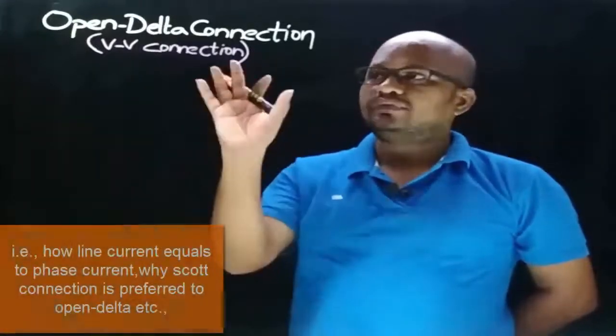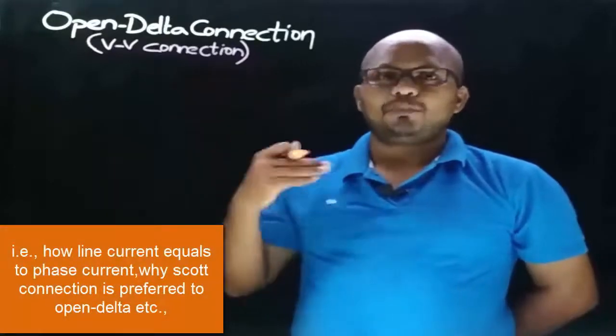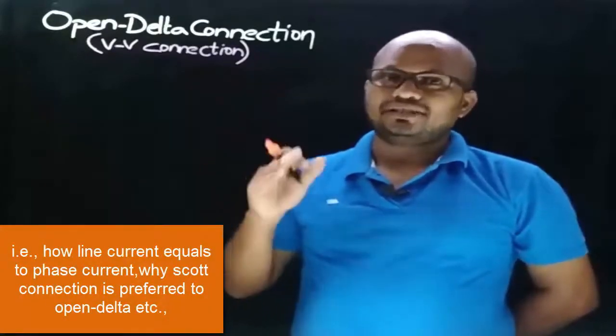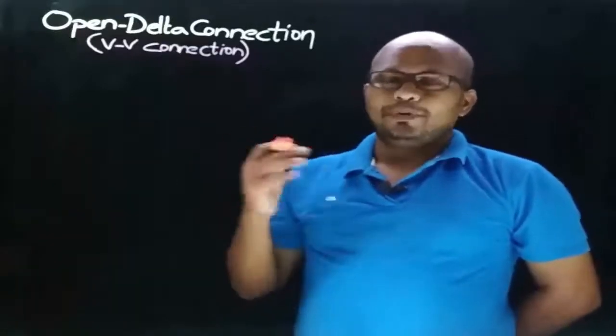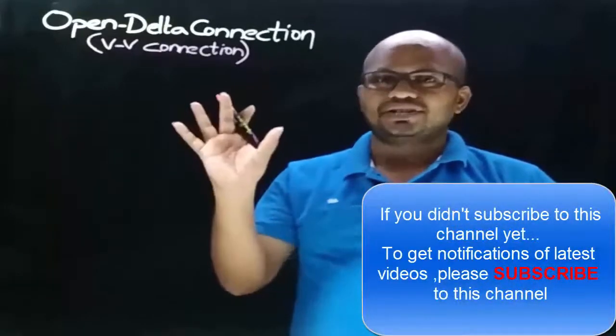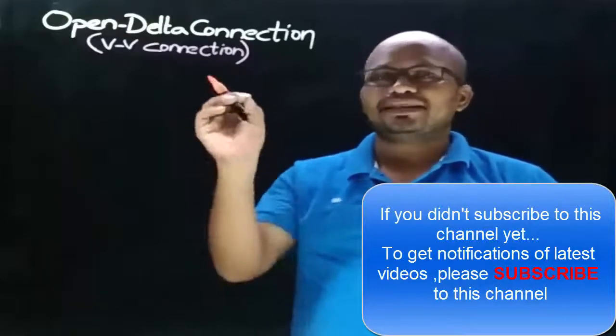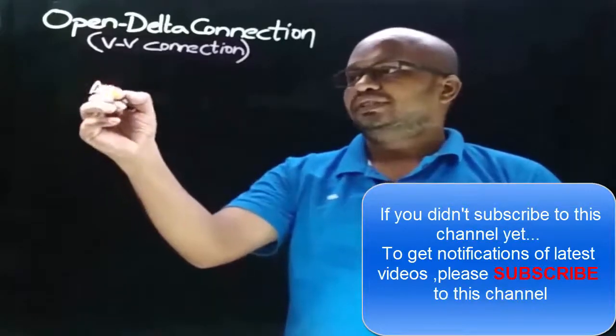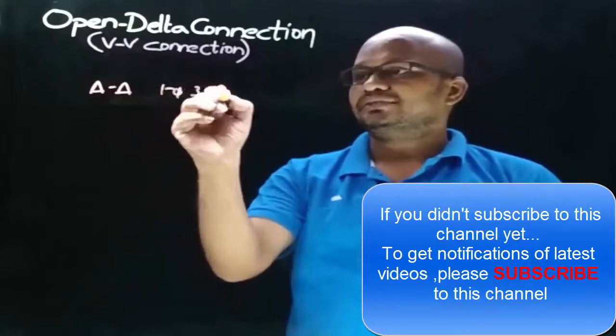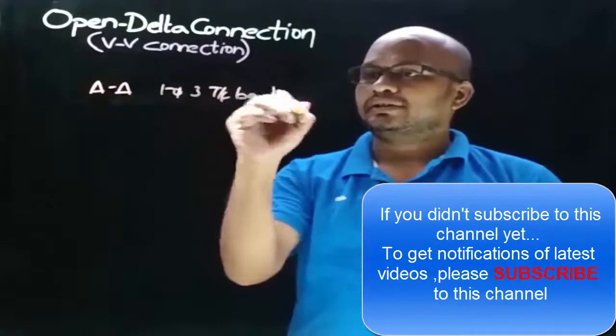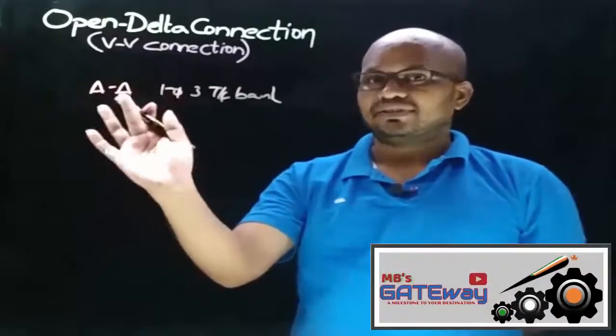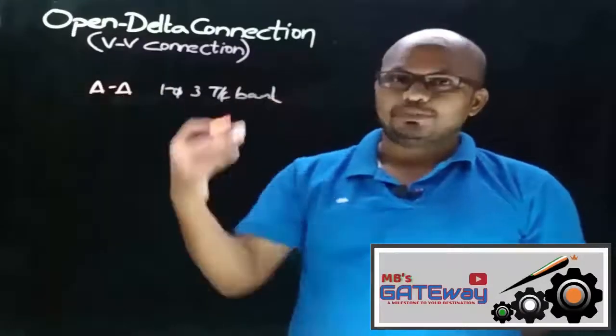That is how one of the transformers in Open Delta connection operates in 30 degrees lead and the other transformer in 30 degrees lag. Open Delta connection is also called VV connection, and a few others simply refer to this as V connection. Open Delta connection is used where one of the transformers in a delta-delta connected single phase 3 transformer bank gets failed. That is, if one of the transformers in delta-delta connection gets failed and the continuity of supply is to be maintained, in that case open delta connection is used.